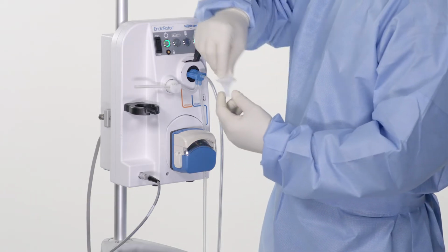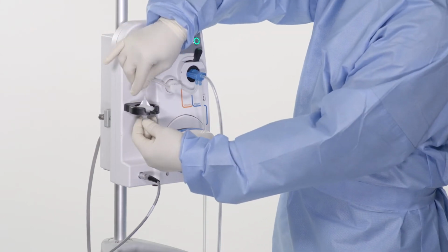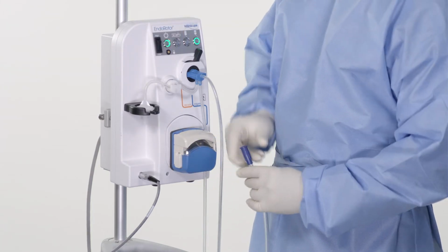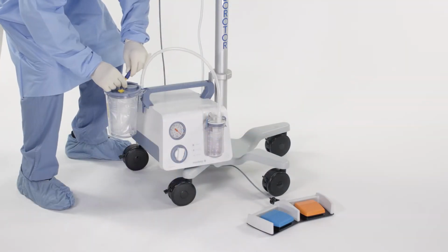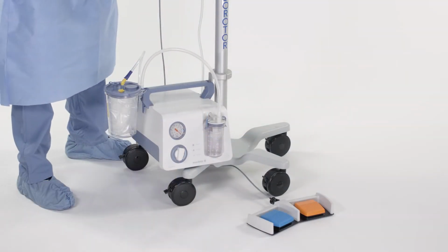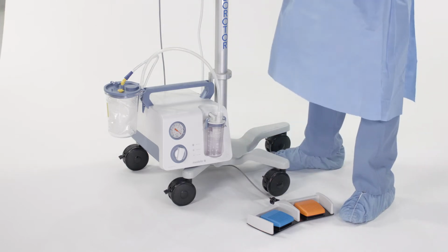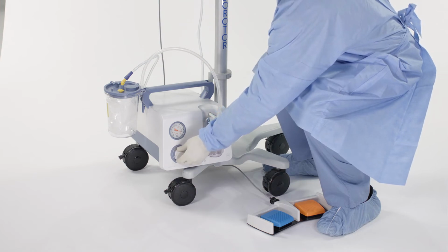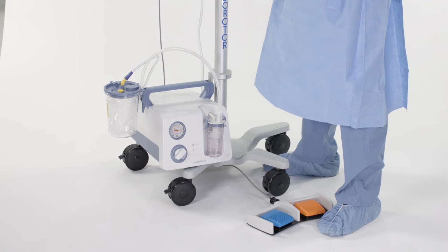Connect vacuum tubing directly to the top section of trap with a press fit until firmly seated. The bottom section of the specimen trap must be connected to vacuum tubing. Remaining tubing will be connected to an independent vacuum. Activate the independent vacuum by pressing the bottom right power button once. Control the suction by turning the dial clockwise, counterclockwise, referencing the inner orange numbers.